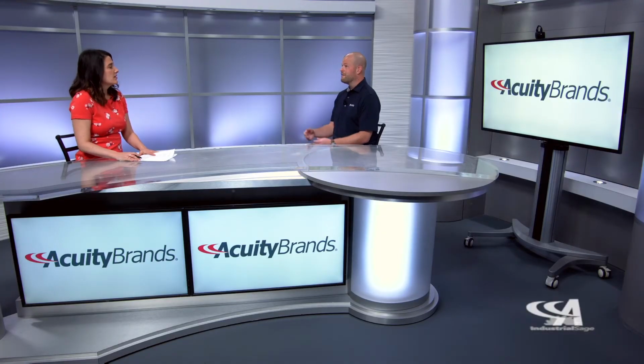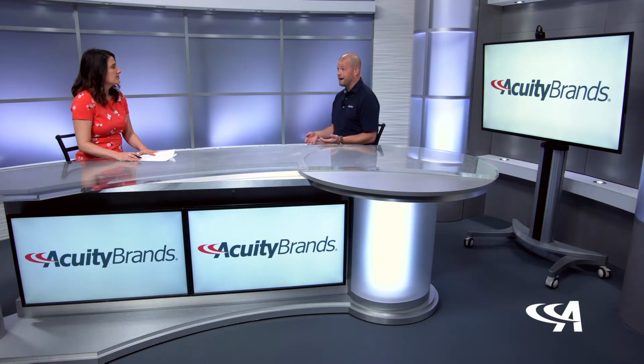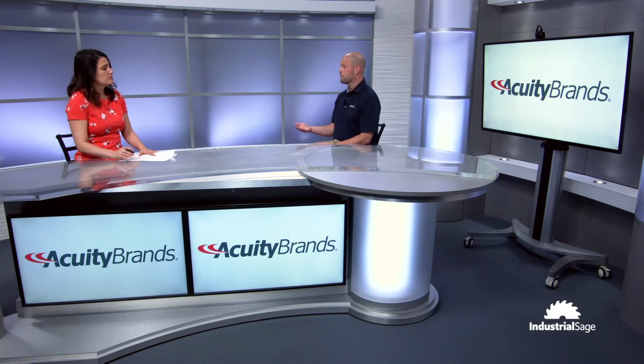Exactly. To be a proper life safety product, it must have a UL 924 certification. To get this certification, that fixture needs to have at least 1 foot candle on the floor for a minimum of 90 minutes. This test is done in a pretty closed environment, so just because you have a UL 924 certification doesn't mean it's the end-all be-all, that it works for all applications, right?